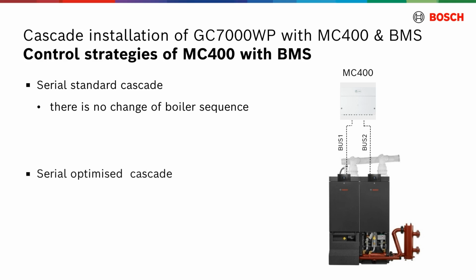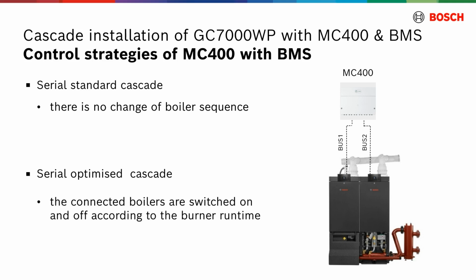Serial optimized Cascade. The aim of this control strategy is to operate the heat generators with equivalent burner runtime. The connected boilers are switched on and off according to the burner runtime. The boiler with the shortest burner runtime is switched on first, and the one with the longest runtime is switched on last. The burner runtime is compared every 24 hours, and the sequence is re-established.